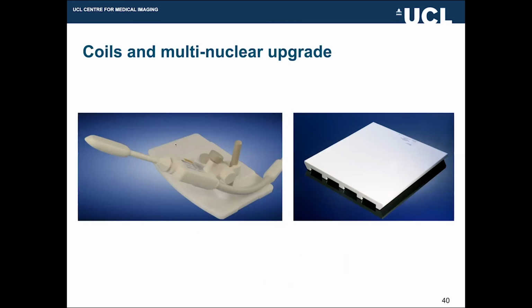Then you need to change your MR machine, because actually MR machines produce signal using protons on water, and they're not really set up to do carbon-13 imaging. So you need to buy specialist coils, and you need to upgrade your MR machine to get signals from a different frequency from carbon-13. So this coil is essentially our first version of an endorectal coil, which was delivered to us and commissioned specially for prostate work. It's now got smaller since then, which was based on patient feedback.